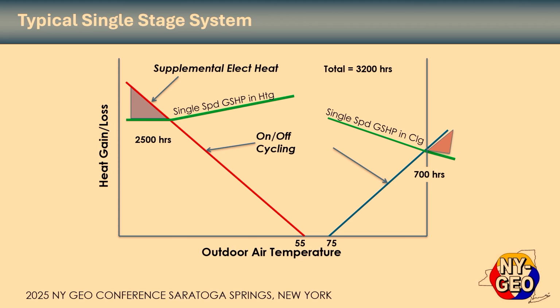Now, this is a ground source heat pump, but an air source would really look very much similar, at least in the way the lines will intersect. So if you can see here, this is a single speed, and so you can see the capacity of the unit based upon the lighter loads is higher, and then it drops down as the outdoor temperature drops down. Typically for ground source heat pump, it's because the loop temperature drops. For an air source, it's because the outdoor temperature is getting colder.